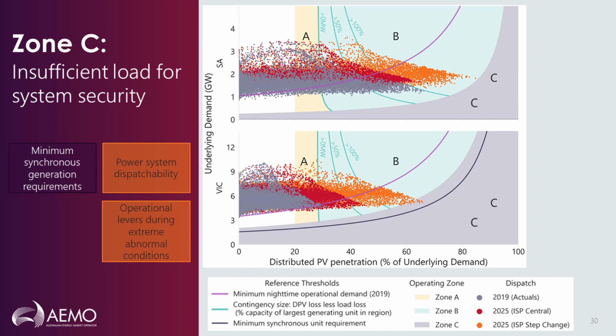Thanks, Drew. So now on to Zone C. Zone C marks the point where operational demand has reduced to such a level that there's not enough load to support minimum synchronous generation requirements. As discussed previously and in other webinars in this series, a certain level of synchronous generation is required to be online at all times in order to have sufficient essential power system security services available. The provision of required system strength, inertia, and frequency control ancillary services is the limiting factor in this case. This provides a hard limit to DPV generation online. If and when we were to get close to this point, we have very few levers available as we cannot reduce DPV generation. Taru will now go through a case study for the South Australian region that demonstrates the urgent need for sufficient backstop mechanisms to be in place if quite extreme abnormal system conditions were to take place during periods like this.